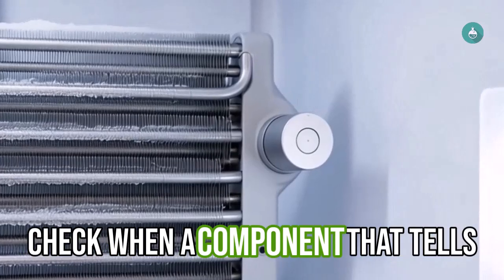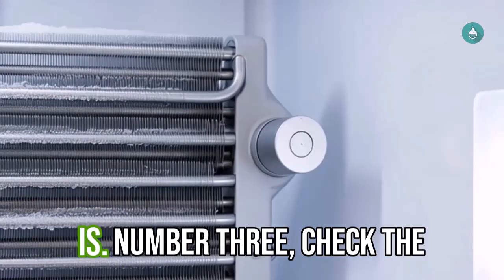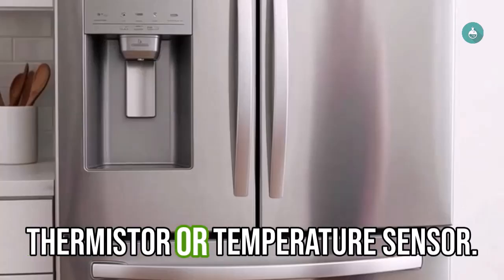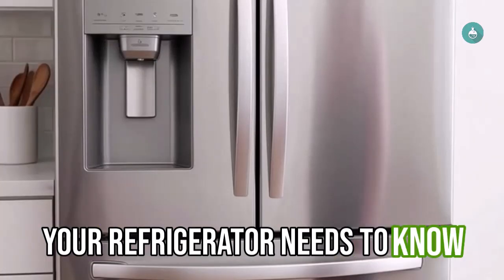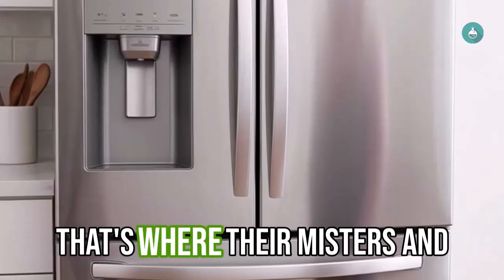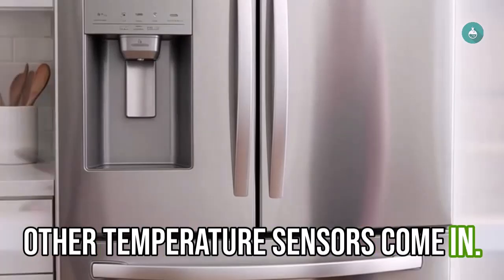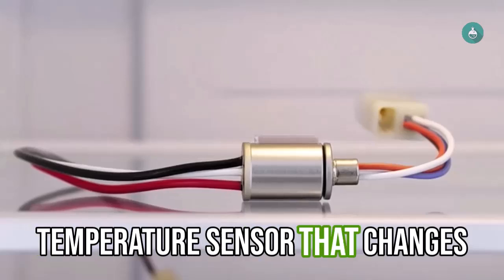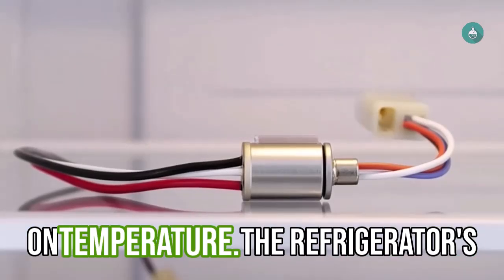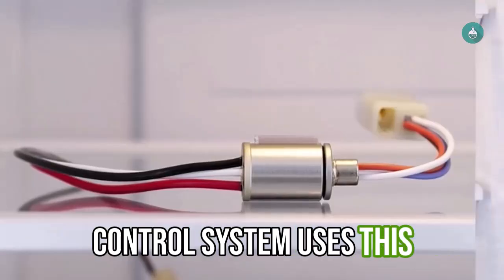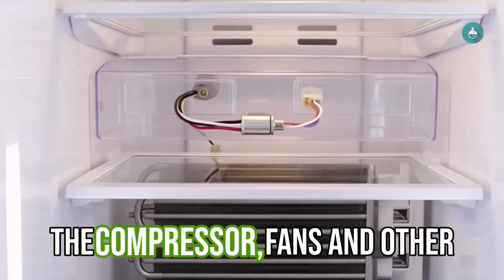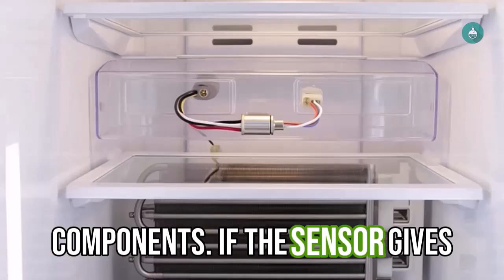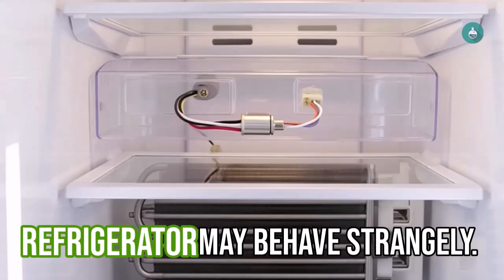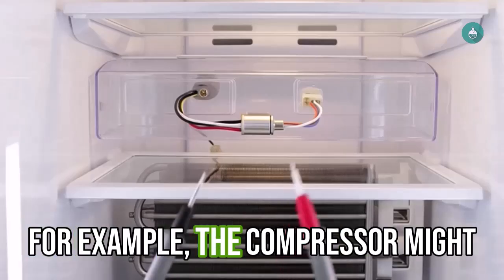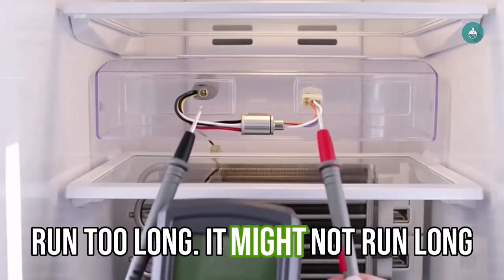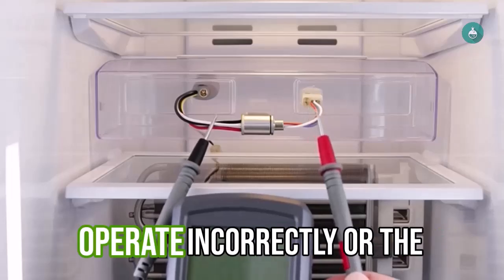Now, let's check one of the components that tells a refrigerator how cold it actually is. Number 3, check the thermistor or temperature sensor. Your refrigerator needs to know the temperature inside the cabinet. That's where thermistors and other temperature sensors come in. A thermistor is an electronic temperature sensor that changes its electrical resistance depending on temperature. The refrigerator's control system uses this information to decide when to run the compressor, fans, and other components. If the sensor gives incorrect information, the refrigerator may behave strangely. For example, the compressor might run too long. It might not run long enough. The evaporator fan may operate incorrectly.